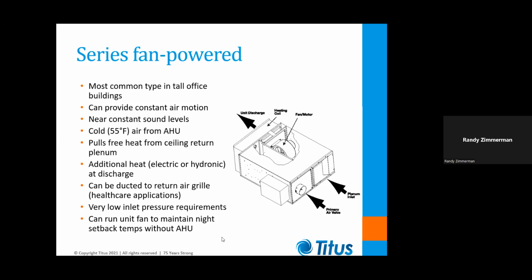Now, another thing about series fan-powered boxes is they have very low inlet pressure requirements, because the air handler only has to move air to the box, and then the fan on this unit picks up the air and moves it the rest of the way to the room. So you can think of this as being like a booster for the air handler. Series fan-powered boxes can actually run with inlet pressures as low as ½ an inch, as opposed to the inch or inch and a half that you might be using for other types of VAV boxes.